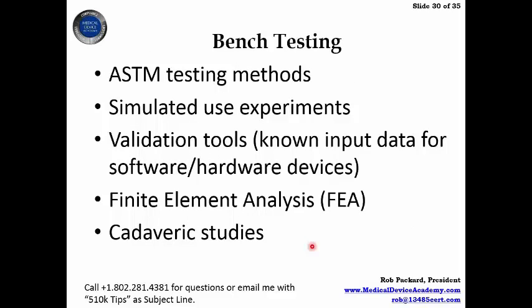For bench testing, here's the different types of bench testing you might do. Finite element analysis is something that's done all on the computer, so it's not cheap, but at the same time, it can be done very quickly and iteratively as you make changes to your design. This gets very expensive, so you usually leave this for the end, and you might have some validation tools if you have hardware or software. So you put in a known set of data and expect a known output.